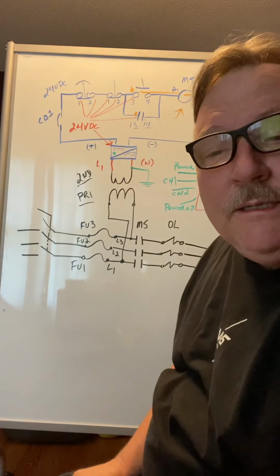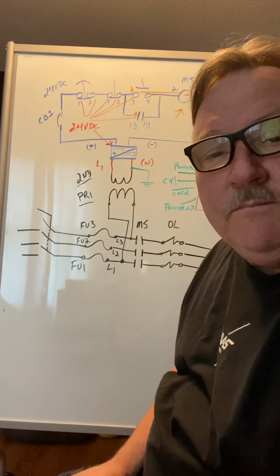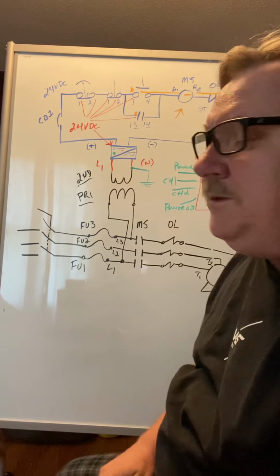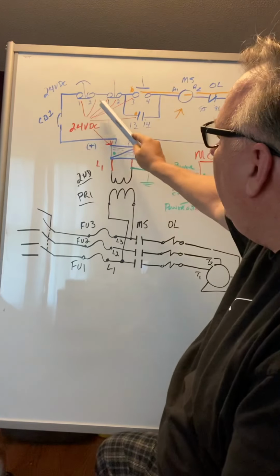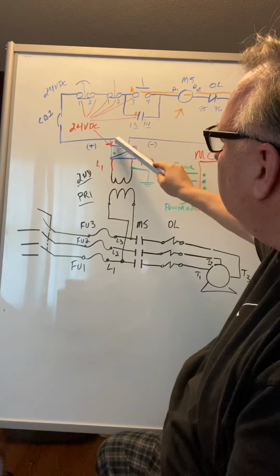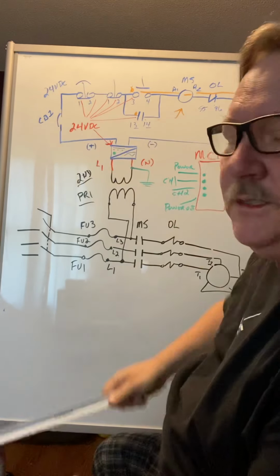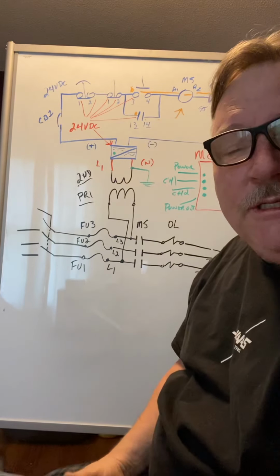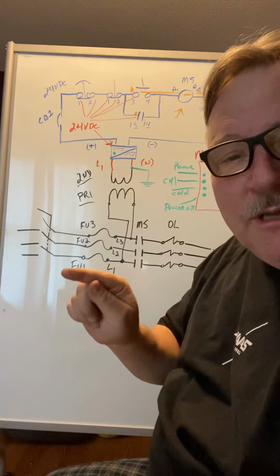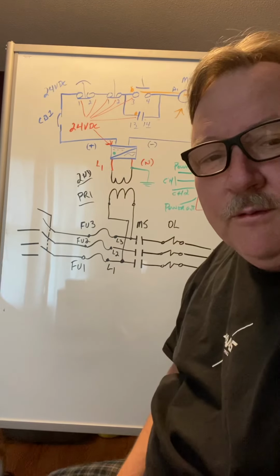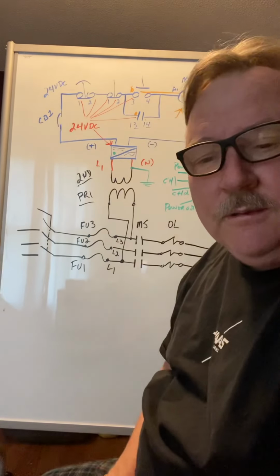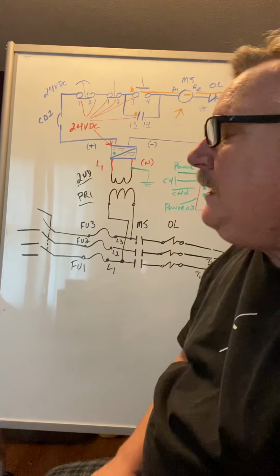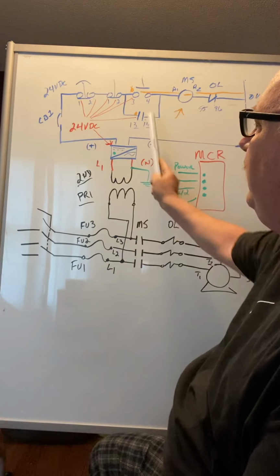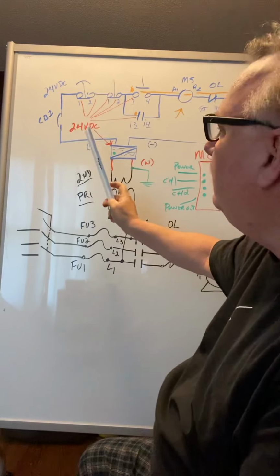All right, introduction to troubleshooting a motor control system. Where you see these red lines going to these terminals, the machine is in its on state, the machine is on, but your machine's not running. Very common how it presents to you as a technician when you go out there and the operator says it doesn't work. But before you get into doing anything with your meter, do a visual check.